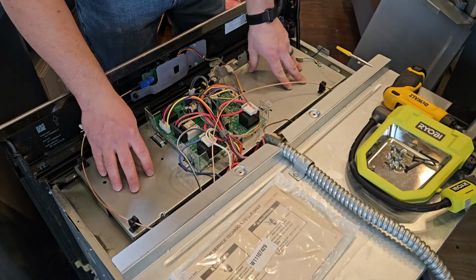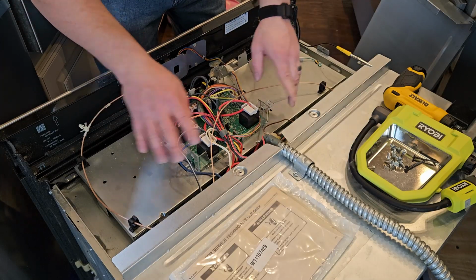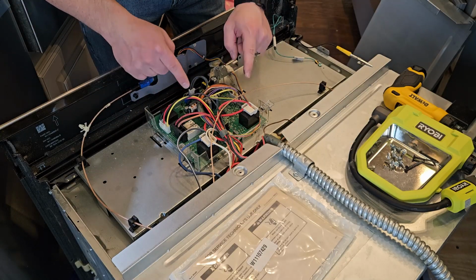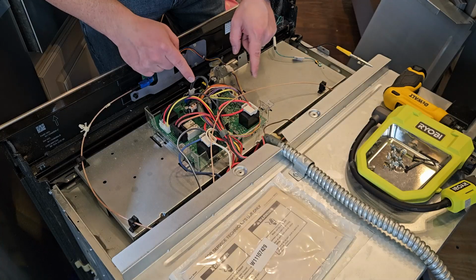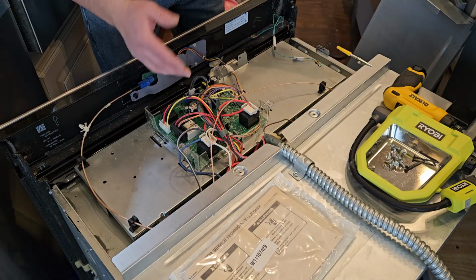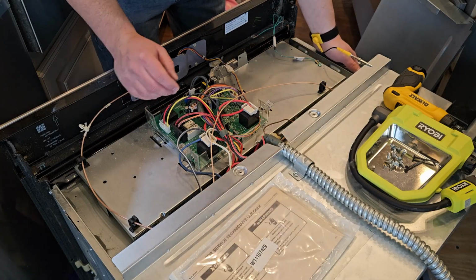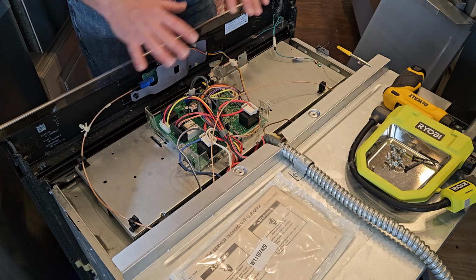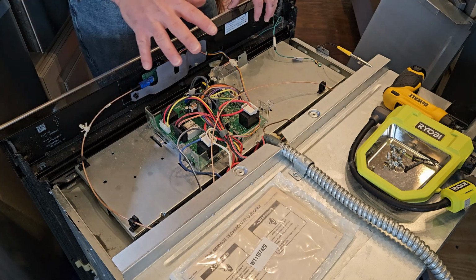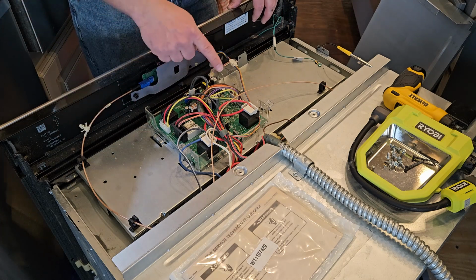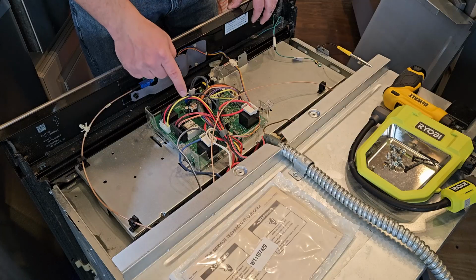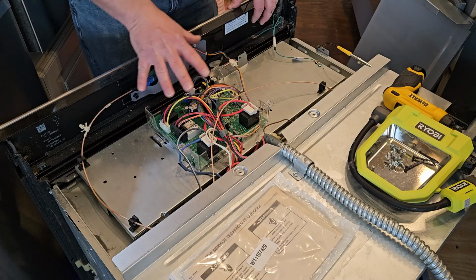And I've already verified the oven power is off because here are a bunch of high power relays that you don't want to mess with if you're not sure that the oven power is off. And at this point, I would recommend before you disconnect anything, take a photo of your layout so you've got a reference you can come back to later and figure out where everything is supposed to plug into.